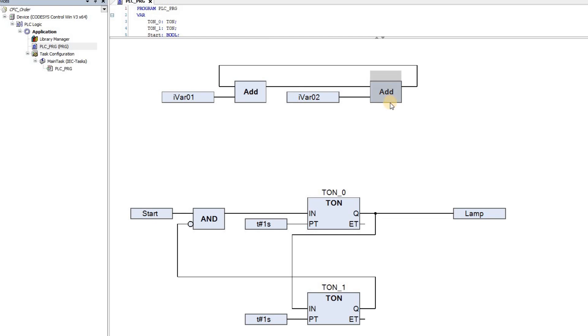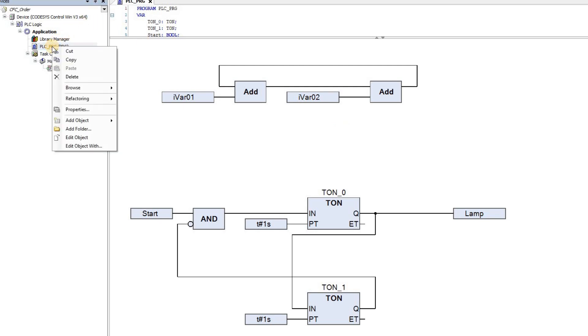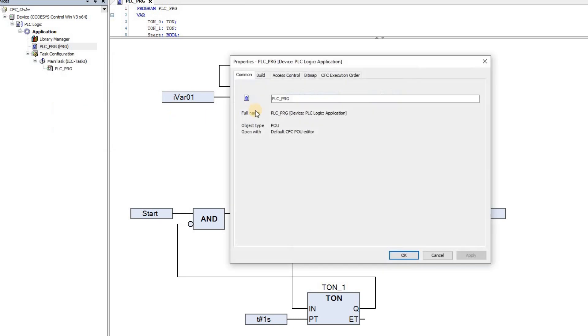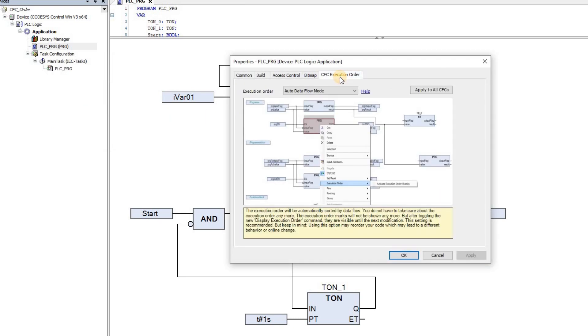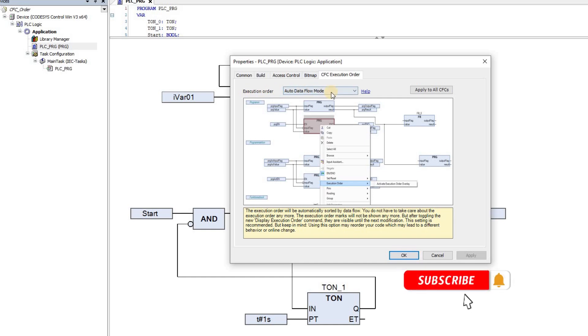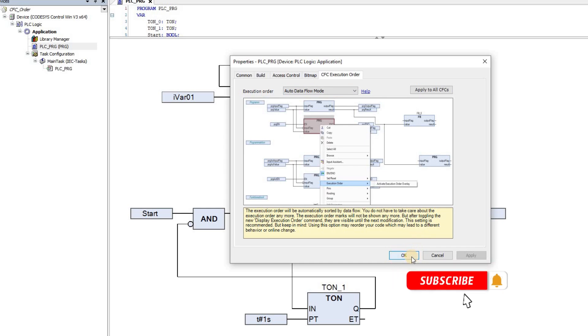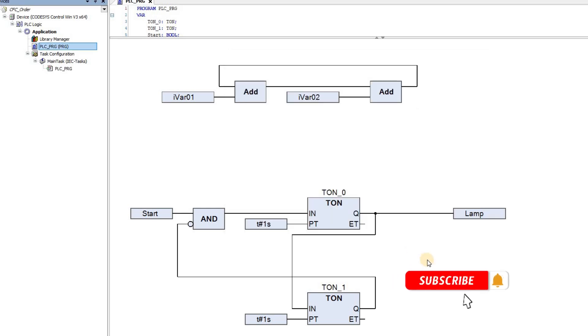By default, the execution order is based on the data flow. We can check this by right-clicking on the POU, choosing Properties. In the CFC execution order tab, in the execution order field, we see that auto data flow mode is selected. So this is the default execution order mode. In this mode, the order in which the blocks are executed is determined based on the data flow.